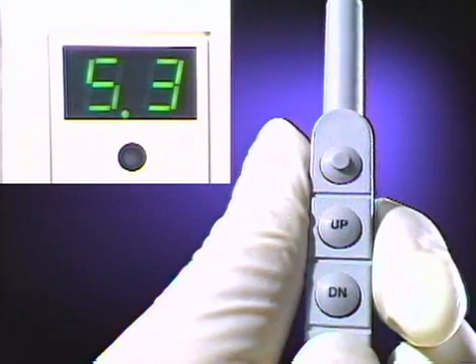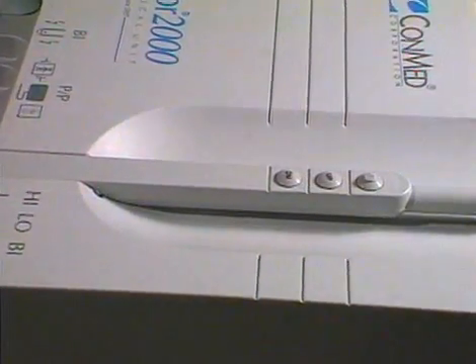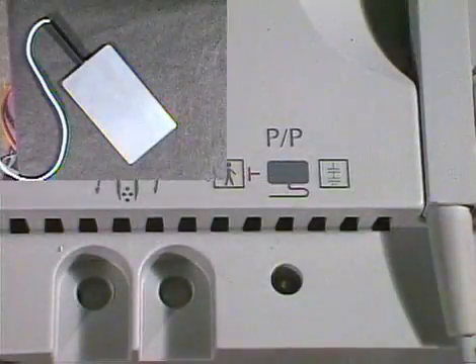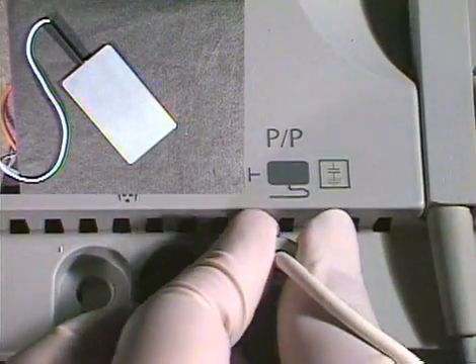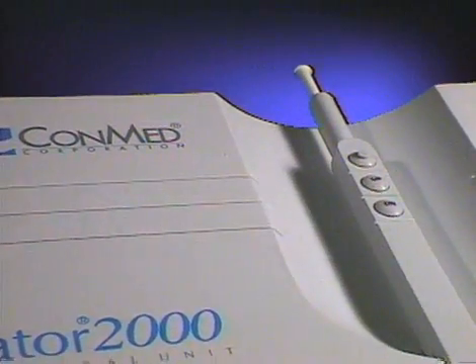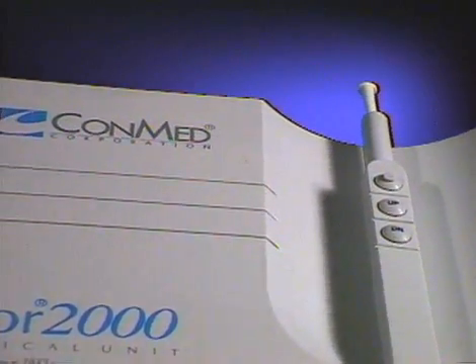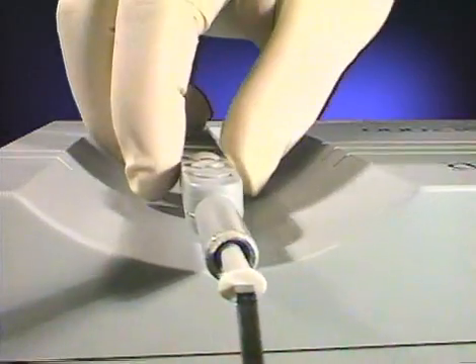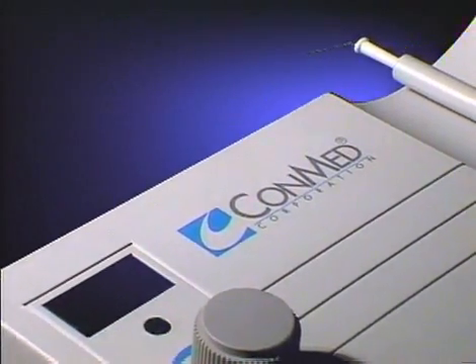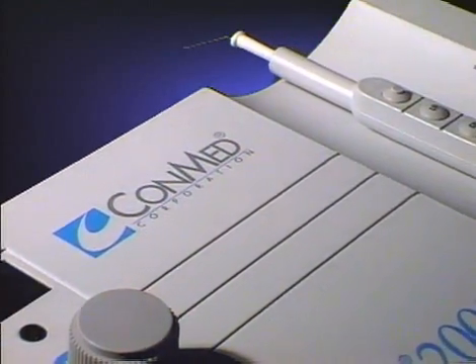Power changes are delivered right to your fingertips through the remote control buttons located conveniently on the pencil. A patient plate has been added for increased power applications. Combining sophisticated control with practical function, the Hyfrecator 2000 will enhance your skills in a wide range of electrosurgical techniques, instilling confidence in you and your patients.